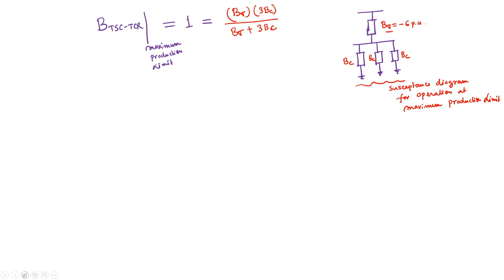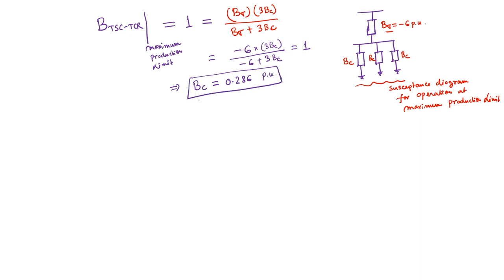Now if you put these values, because we know B sigma is equal to minus 6, this will be minus 6 multiplied by 3 BC divided by minus 6 plus 3 BC. This is equal to 1. So this gives the value of BC, which is equal to 0.286 per unit. This is the susceptance rating of a particular TSC unit.